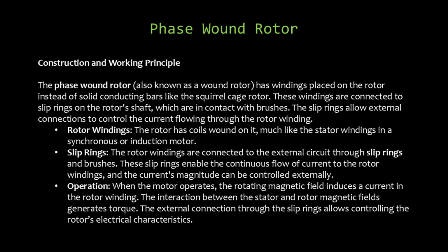Coils are wound on the rotor, similar to stator windings in synchronous or induction motors. Slip rings and brushes enable continuous current flow to the rotor windings, with the ability to control current magnitude externally. When the motor operates, the rotating magnetic field induces current in the rotor winding, generating torque through magnetic field interaction.